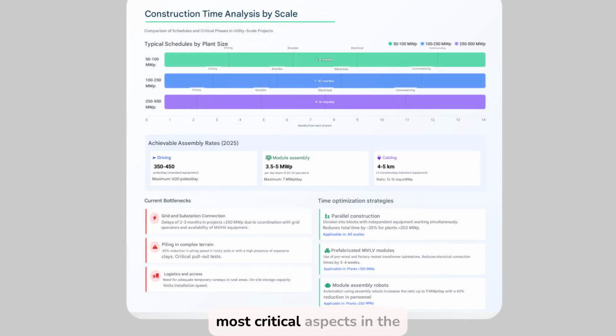Now we address one of the most critical aspects in the execution of utility-scale photovoltaic plants: actual construction schedules and how they vary depending on the scale of installed capacity. This is where the difference between a successful project and one with cost overruns, contractual penalties, or the loss of grid connection opportunities lies. Let's look at the top. 50-100 MWp plants can be completed in 5 to 8 months, including piling, assembly, and electrical wiring phases. 100-250 MWP plants: the duration increases to 7 to 10 months. 250-500 MWP plants take between 9 and 14 months, with longer phases due to the substation and commissioning.